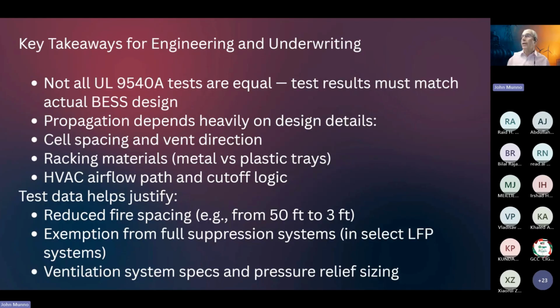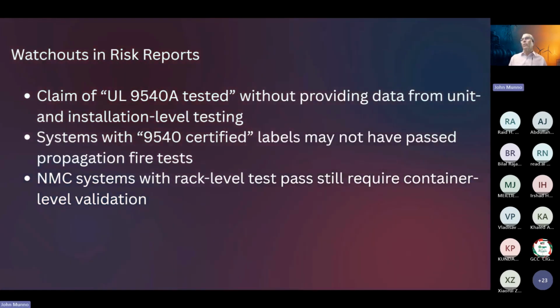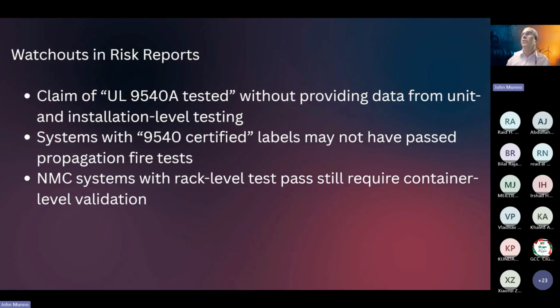So the data helps us reduce the fire spacing from as much as 50 feet down to 3 feet if you can work in that space. And it exempts us sometimes from full suppression systems if we have a good test. So the data from these tests is very important for helping us finish our design on our system. And that's why we can't wait till we've already finished the design and then go get a test.